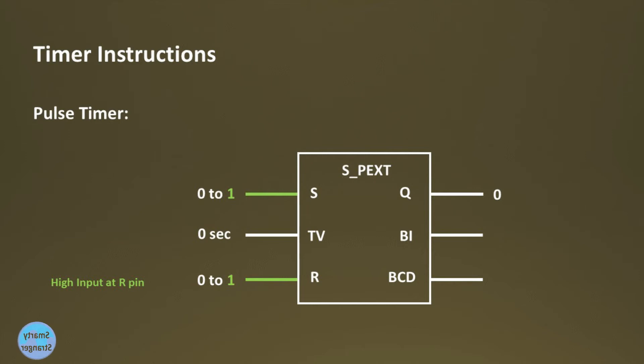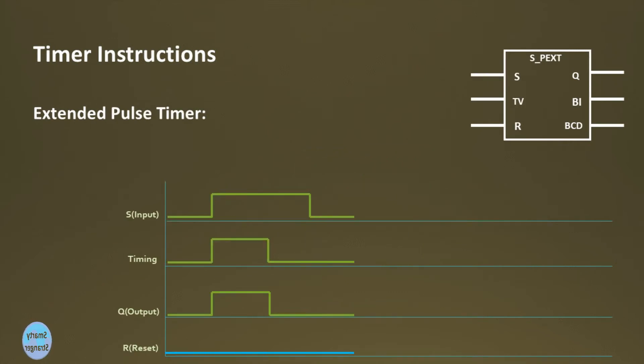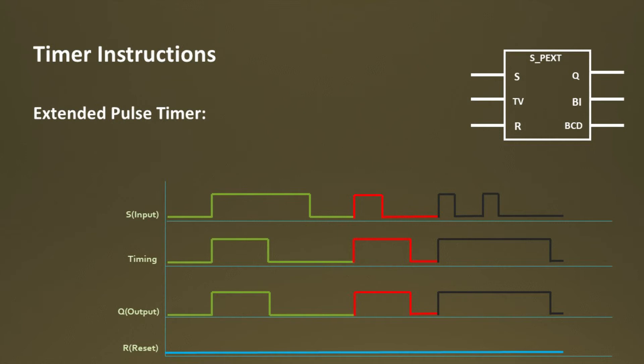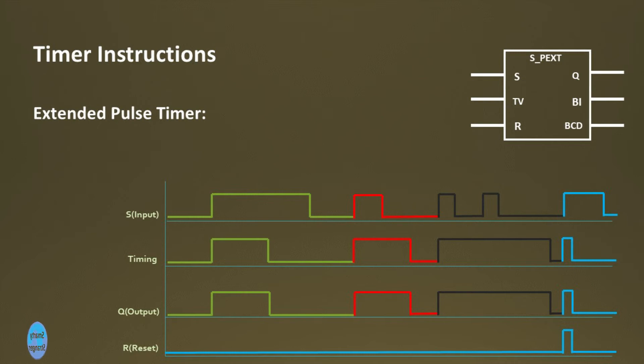Let's understand the Extended Pulse timer via trends view. In the first cycle, if there is a positive edge at S input, the timer starts its timing and output Q gives 1 or high — it remains 1 as long as the timer is running. In the second cycle, if S input changes from 1 to 0 before time elapsed, the timer completes its timing and output Q remains 1. In the third cycle, if there is fluctuation on pin S, the timer remains running and output Q remains 1 until time elapses. In the fourth cycle, if input R changes from 0 to 1 while the timer is running, the current time and output Q are set to 0.